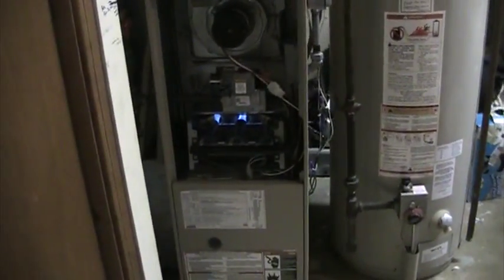All right, the blower just kicked on, the blower is on medium speed for heating. This camera doesn't zoom too great in the line. Anyways, so that's that. Draft inducer came on first, then pressure switch verified, igniter came on, gas valve burners, and the blower.